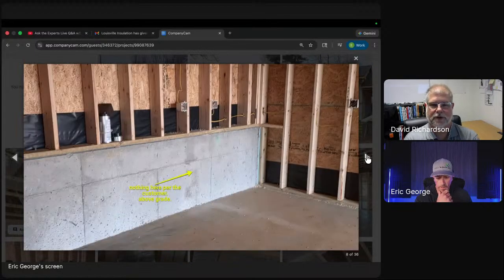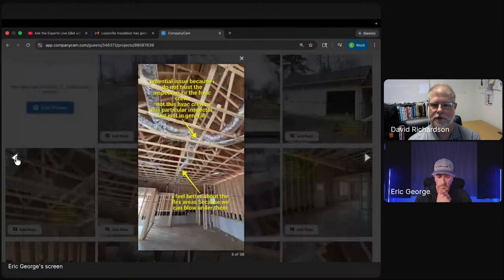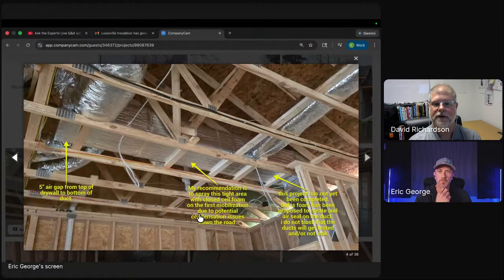Going back to the original question about putting closed cell foam underneath: if this is an unconditioned attic with a second type of insulation going in, that's not going to keep the ducts from sweating. It'll just sweat above the closed cell and condense on top of it — it'll just be the first surface it hits instead of the drywall. So the ducts could technically still sweat as long as the temperature in them is at or below dew point.